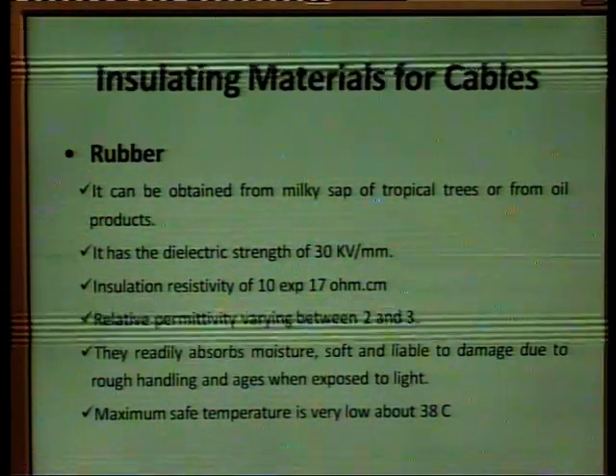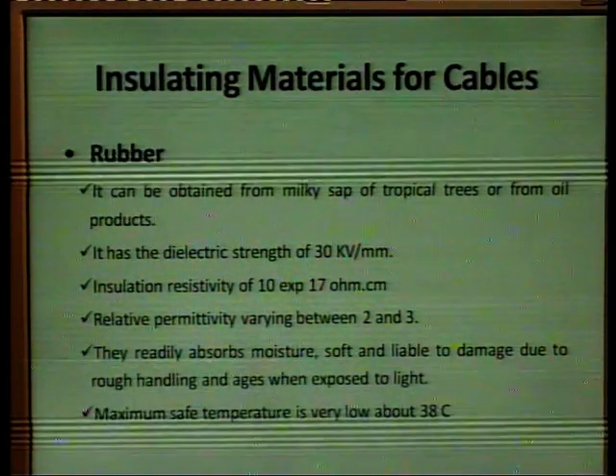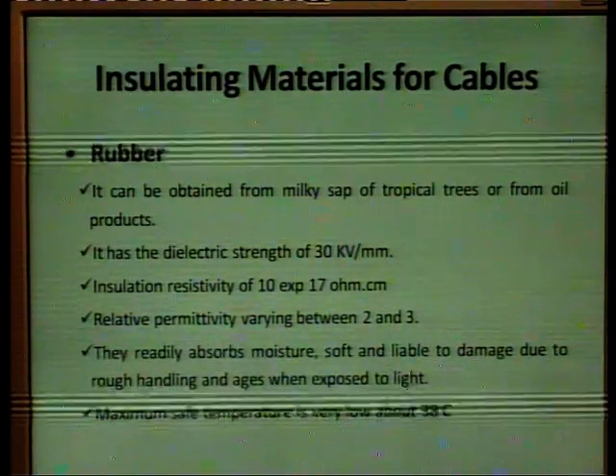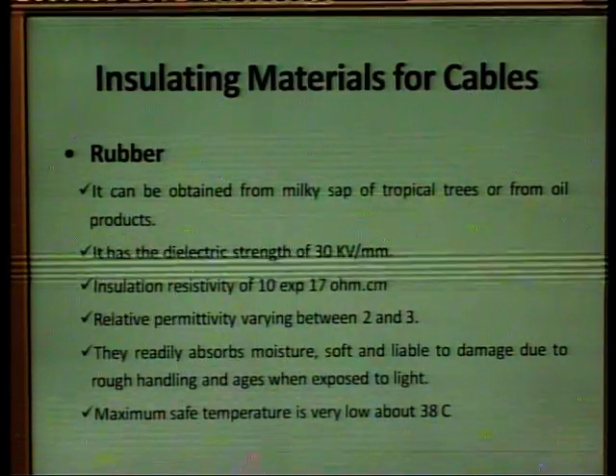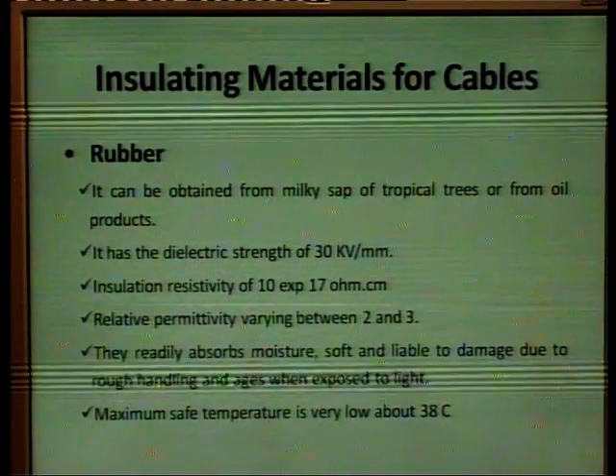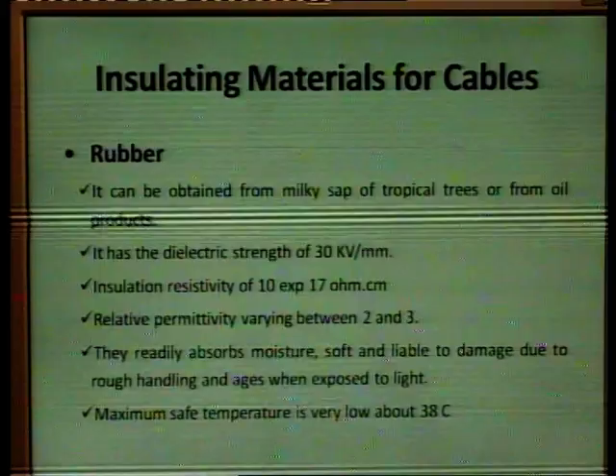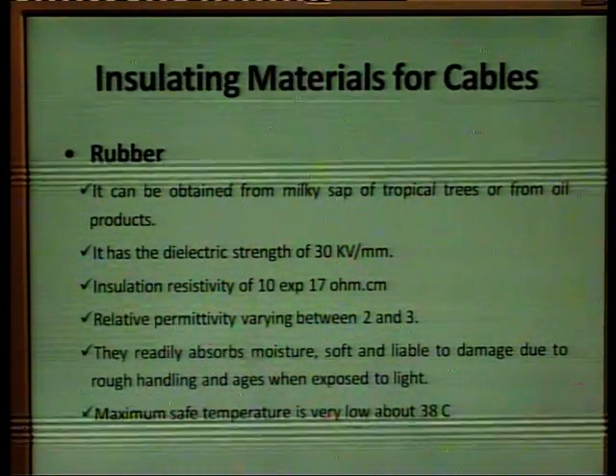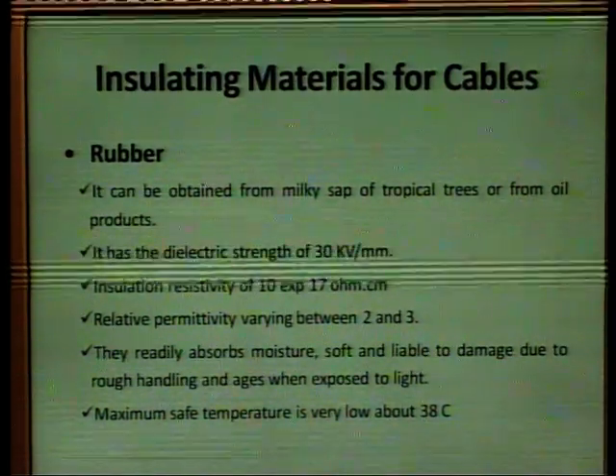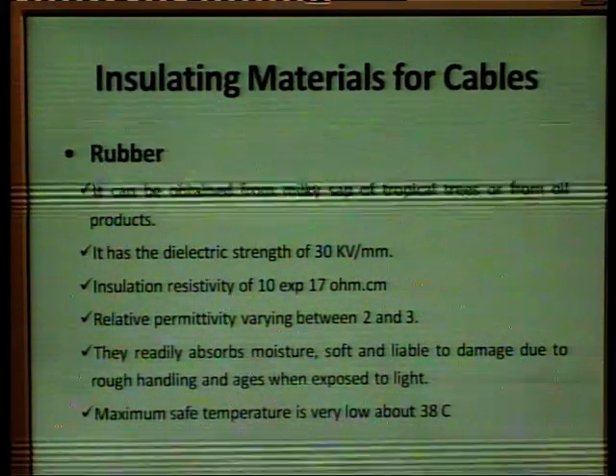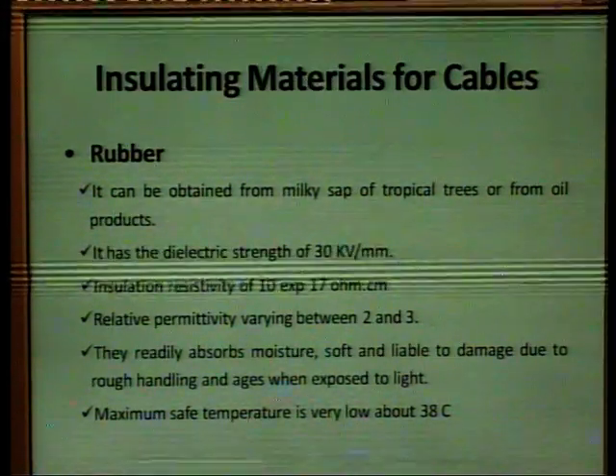Then we have the different insulating materials for the cables. First material we have is rubber. It can be obtained from the milky sap of the tropical trees or from oil products. It has a dielectric strength of 30 kV per mm. Then the insulation resistivity of 10 to the power 17 ohm centimeter is there. And the relative permittivity of rubber varies between 2 to 3. They readily absorb some moisture, are soft and liable to damage due to rough handling, and age when exposed to light. And the maximum safe temperature is very low, about 38 degrees centigrade.